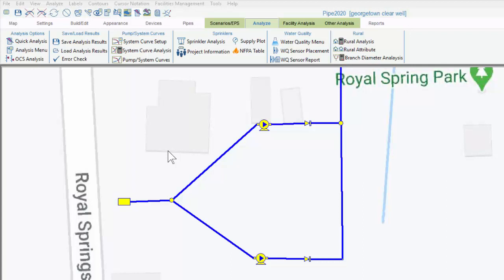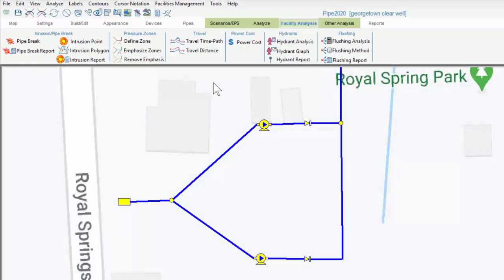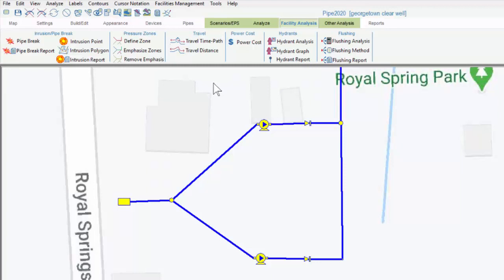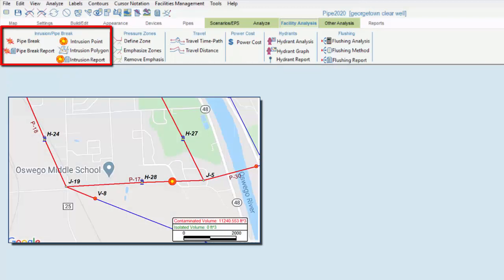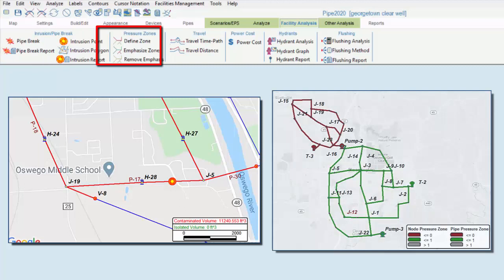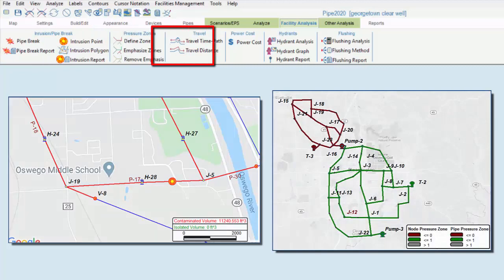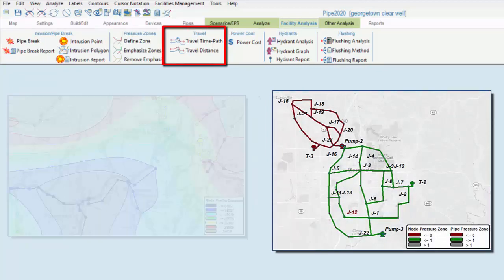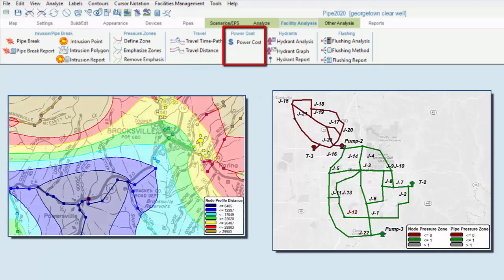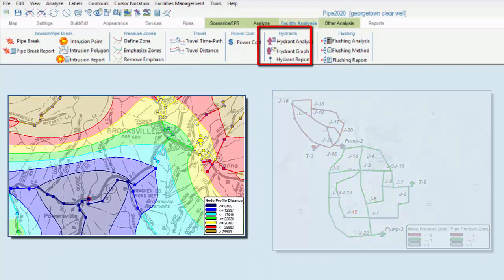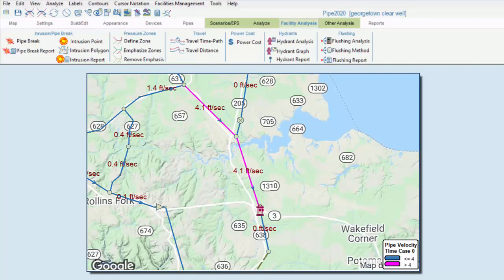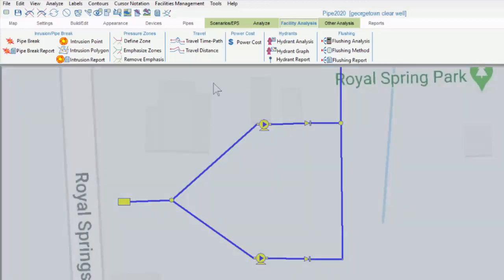The facility analysis tab contains shortcuts for the different analysis types often used by system operators. Some of these can also be accessed from within the analyze tab, but they can be accessed here using fewer steps. We see the submenus for intrusions and pipe breaks, as well as defining pressure zones, travel time and travel path, travel distance, power cost, and hydrant analysis. There is also a hydrant flushing analysis, which returns flushing velocities based on the number and location of open hydrants, and these outputs can be compared to a user specified minimum allowable velocity.